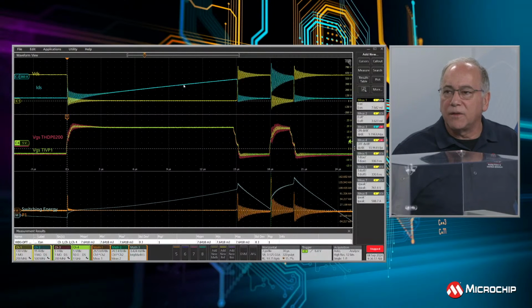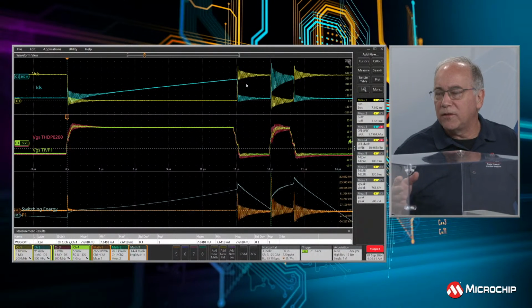Also notice that there's a fairly small amount of time between the first pulse and the second pulse, because when you are freewheeling during the off time, you're freewheeling through the diode, as you had explained before, you lose some of the energy in the inductance, and that will reduce the current. So really you want to make the interval between the first and second pulses as short as possible. You want to make sure the ringing has died down and then provide that second pulse.